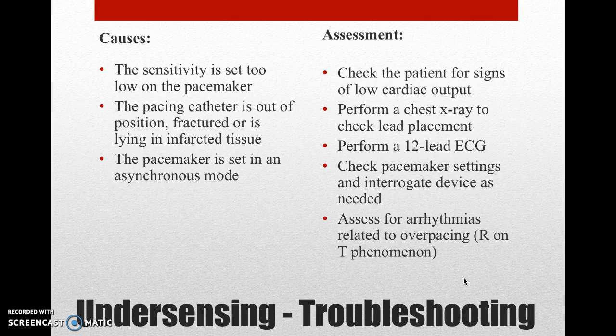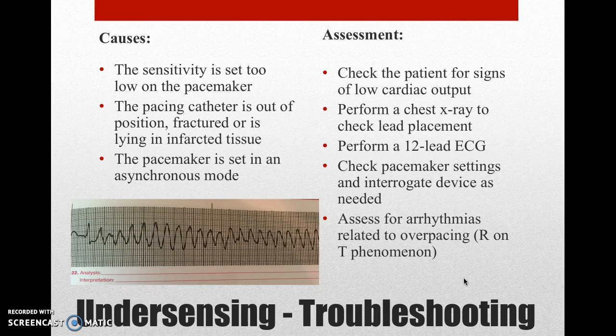Troubleshooting undersensing issues includes determining the cause. Perhaps the sensitivity is set too low on the pacemaker, the pacing catheter is out of position, has fractured, or is lying in infarcted tissue, or the pacemaker may be left in an asynchronous mode. Assessment includes checking the patient for signs of low cardiac output, performing a chest x-ray to check lead placement, performing a 12-lead ECG, and checking the pacemaker settings and interrogating the device as needed.